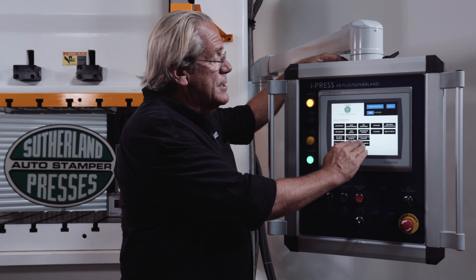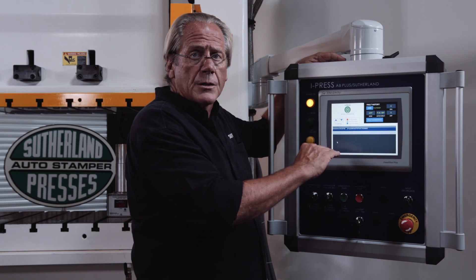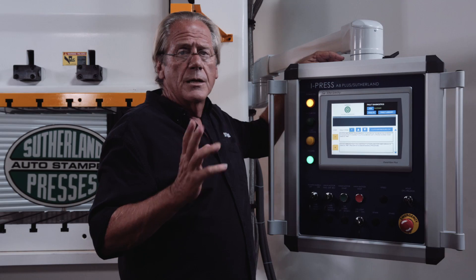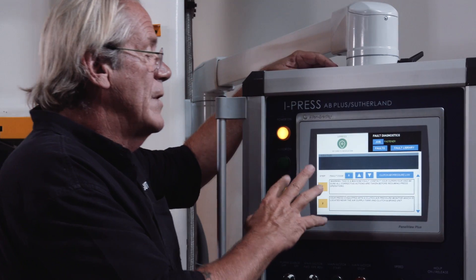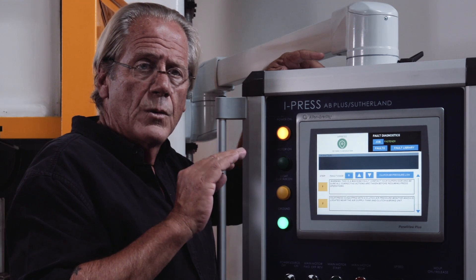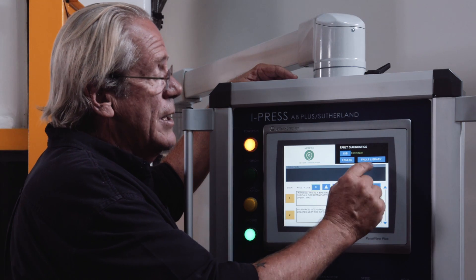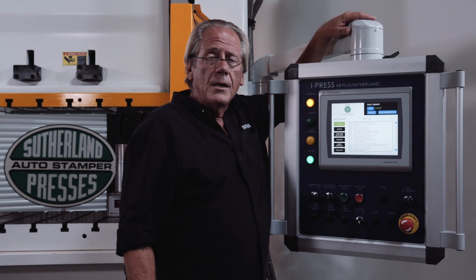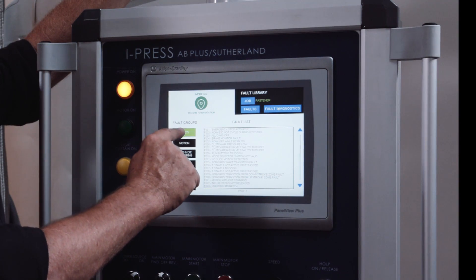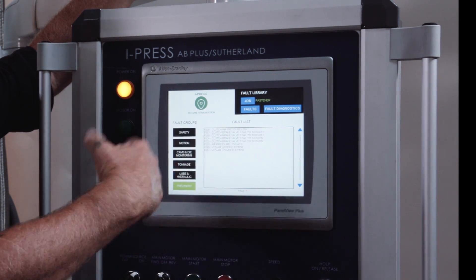Fault history, fault diagnostics, and fault library — this is something that we've grown on the I-Press. Fault history gives you a chronological record of when the fault occurred and when it was cleared. Fault diagnostics: if an operator is unsure of what the fault means, fault diagnostics gives sequential steps for an operator or maintenance personnel to work through — what was the cause and the steps to check first, second, third, fourth to rule out problems. You also have a fault library, designed by the PBE engineering team, broken down into fault groups: safety, motion, cams, tonnage, lubrication, and pneumatic. It gives you the fault code and you can drill back into the diagnostics.